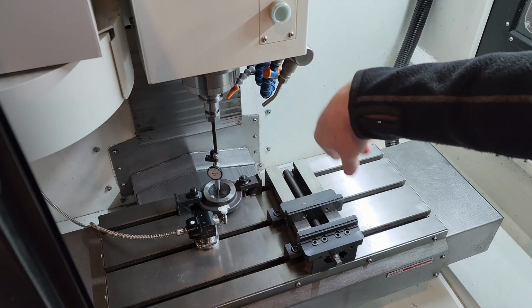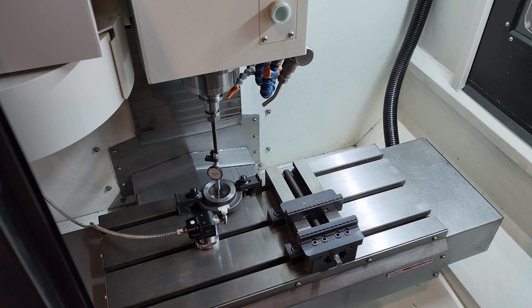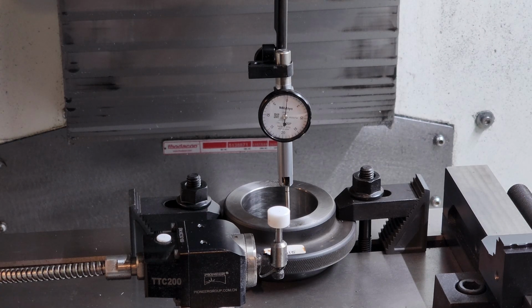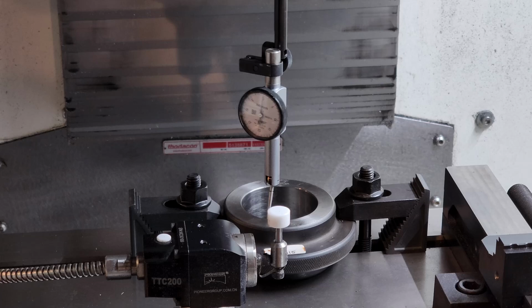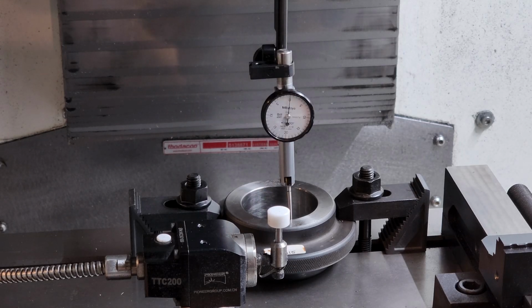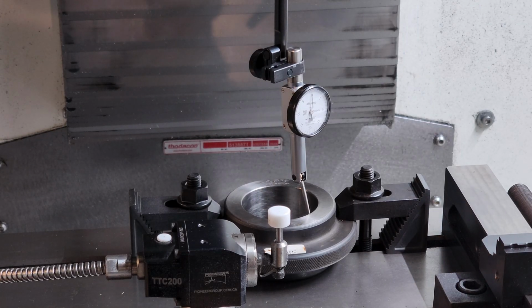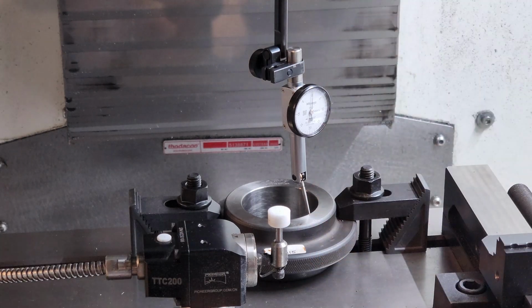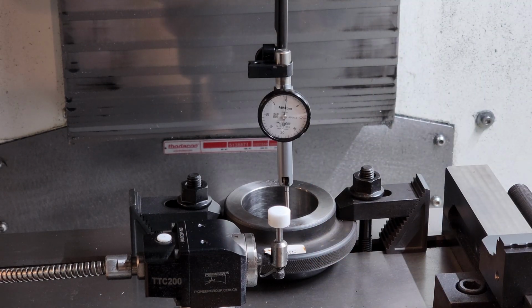First, with the indicator above the ring gauge, rotate the spindle by hand and roughly adjust the dial indicator and the spindle by eye until they are centered above the ring gauge. Next, lower the indicator inside the ring gauge. Using this method, you will need to find 0 in 3 quadrants, left and right of the ring gauge on the x-axis and the front of the ring gauge on the y-axis.